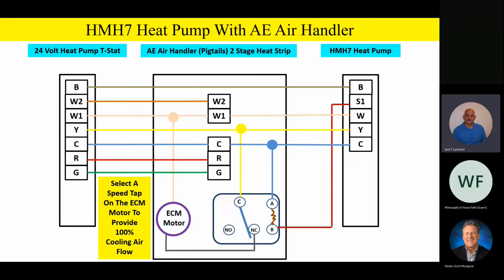Okay. Now watch this on that switching relay. We're going to take the normally open contact on the relay, the normally open contact, and we're going to go over to the motor and we're going to select a speed tap that's going to give us about 60% airflow. Now, when you select that speed tap, let's say you're on speed tap number 3 or 4, or maybe 2 or 3, if you can, you want to get real close to 60% airflow. If it goes up to 65%, that's okay. If it goes down to about 55%, that's okay. So really 60% airflow is kind of the target airflow.